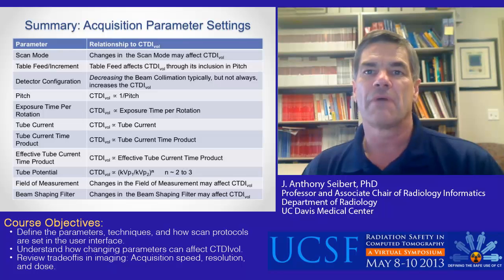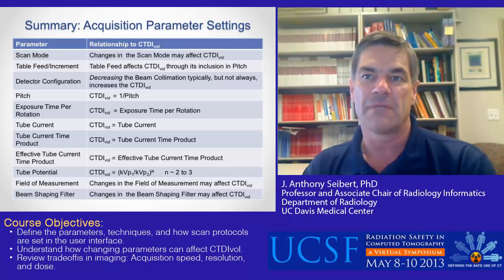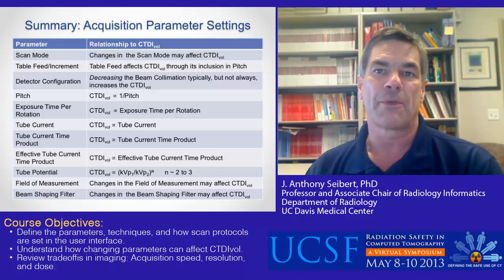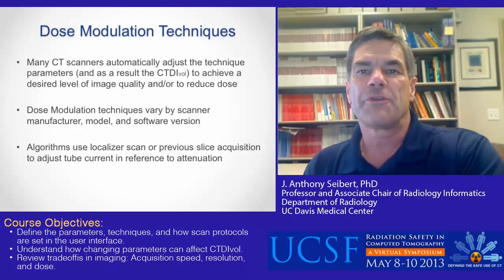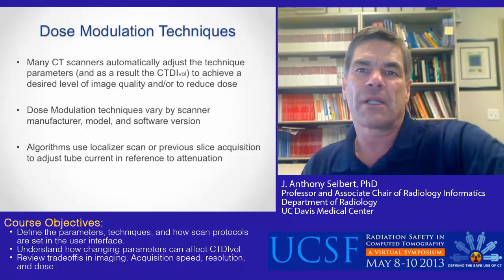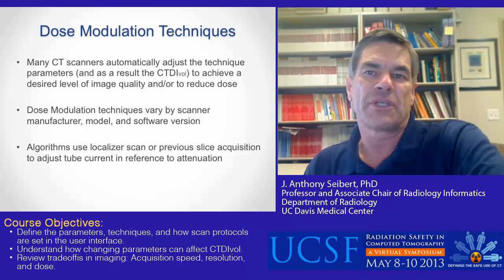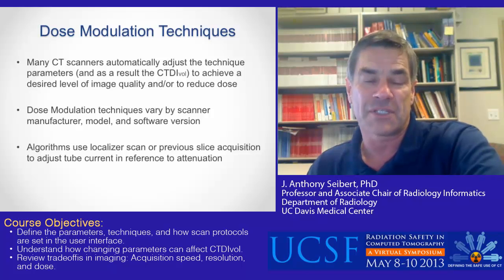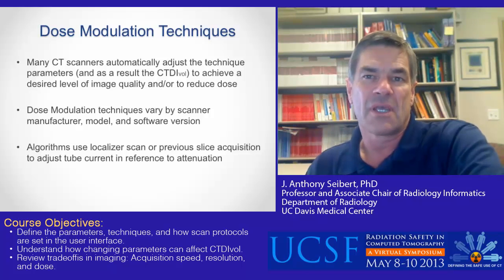A summary of acquisition parameter settings is displayed on this slide. The relationship of each parameter to CTDI vol is given, assuming all other parameters are fixed. Many CT scanners automatically vary the technique factors according to the attenuation variability of the patient habitus, determined either by analysis of the localizer exam or by the previous slice acquisition and analysis of the noise properties of that slice. Thus, use of dose modulation techniques can impact the CTDI vol.